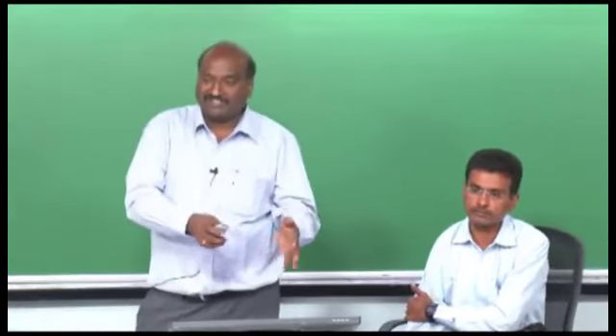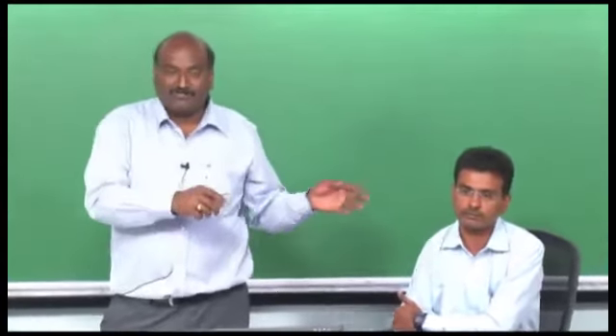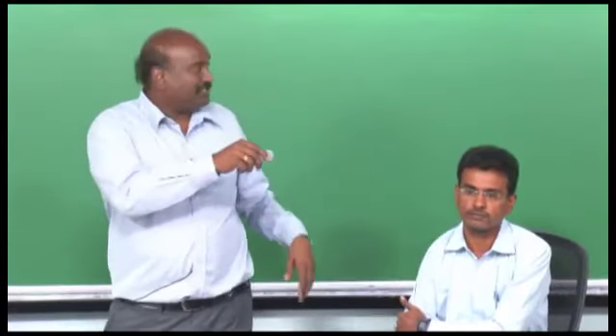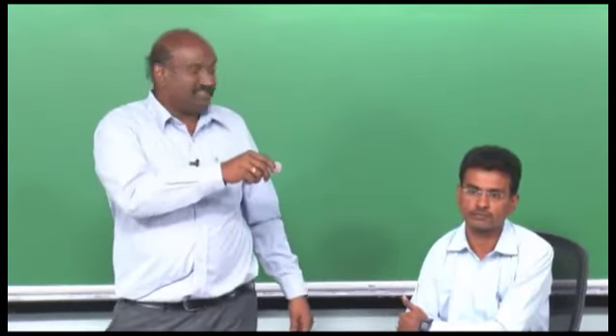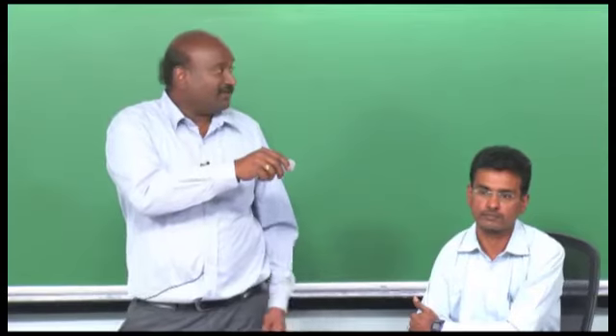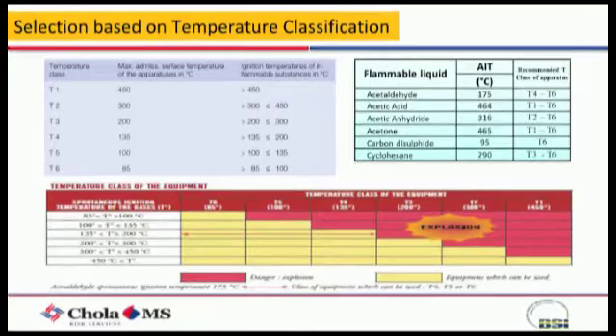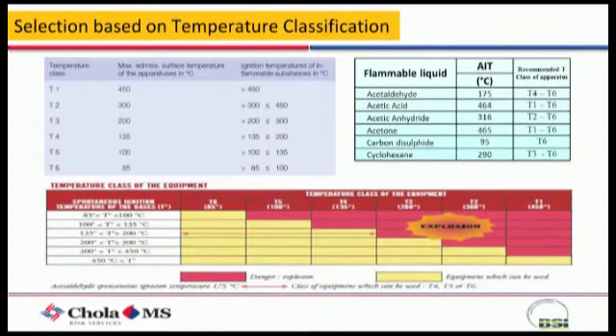with certain surfaces itself. So assume I am buying a motor of say some T1 or T2 or T3, which can go up to 200-300 degree temperature. Put this in an area where a material is being processed and its auto ignition is 140, what will happen? It will immediately catch fire when there is some small spillage on the motor or something, isn't it?